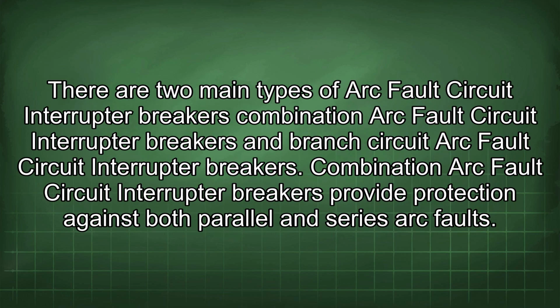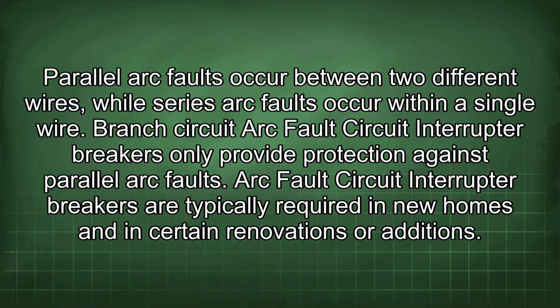There are two main types of arc fault circuit interrupter breakers: combination arc fault circuit interrupter breakers and branch circuit arc fault circuit interrupter breakers. Combination arc fault circuit interrupter breakers provide protection against both parallel and series arc faults. Parallel arc faults occur between two different wires, while series arc faults occur within a single wire. Branch circuit arc fault circuit interrupter breakers only provide protection against parallel arc faults.